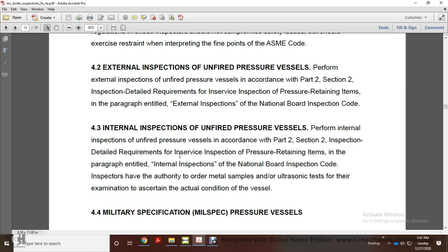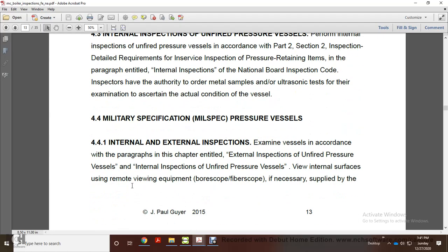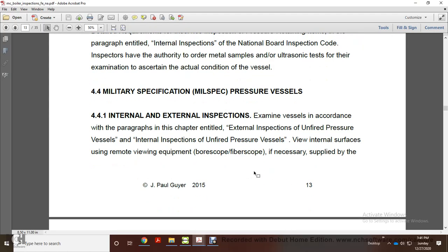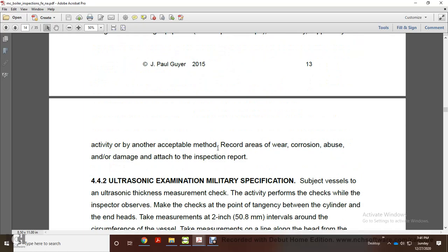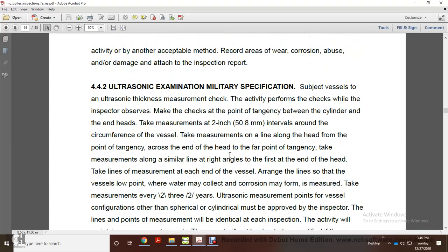And inspectors may have the authority to order metal samples or ultrasonic tests for their examination to ascertain the actual condition of the vessel. 4.4 Military specification pressure vessels, internal and external inspection. Examine the vessel in accordance with the paragraph of the chapter, External inspection for the unfired pressure vessels and internal inspection of unfired pressure vessels. View the internal surface with the remote viewing equipment, borescope/fiberscope, if necessary, supplied by activity or by another acceptable method. Record areas of wear, corrosion, abuse, and any other damage attached to the inspection report.